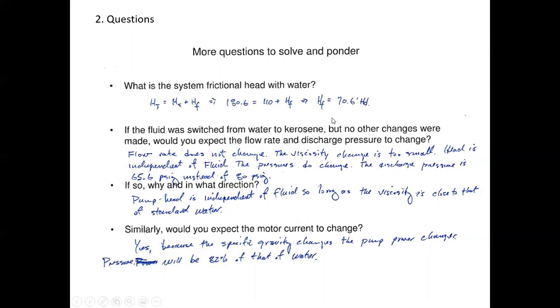If the fluid was switched from water to kerosene, but no other changes were made, and see, that's what's a little misleading. Some of the stuff changes, like the power changes and that sort of thing. And the pump head stays the same, but the discharge pressure changes. And so, if you're not fairly experienced with this, when you read that, you're not sure what to change and what not to change. Flow rate does not change.